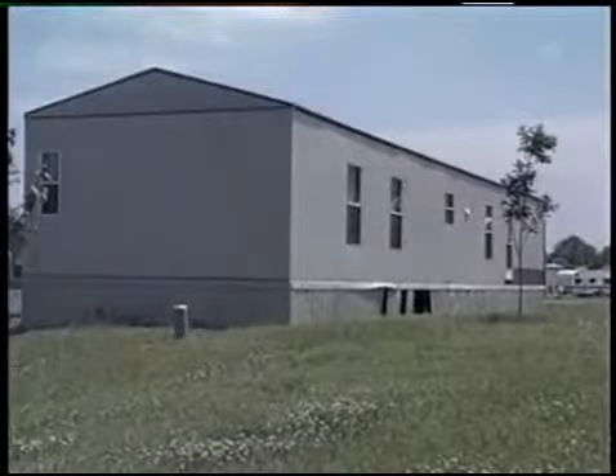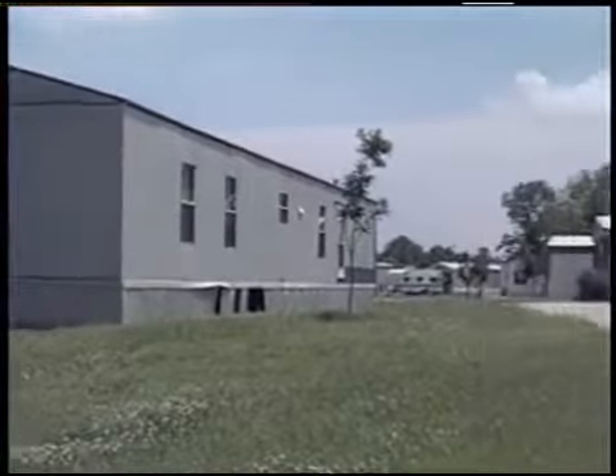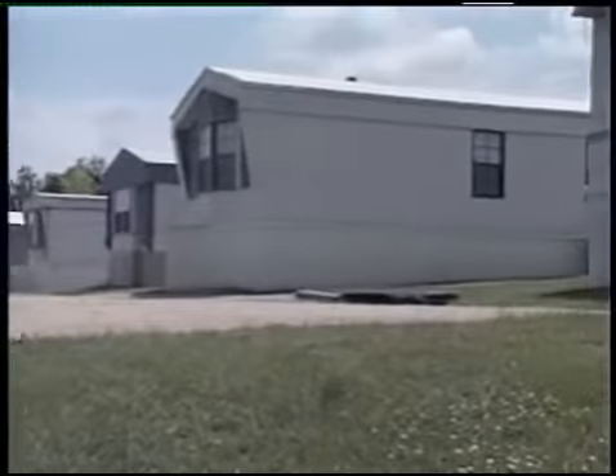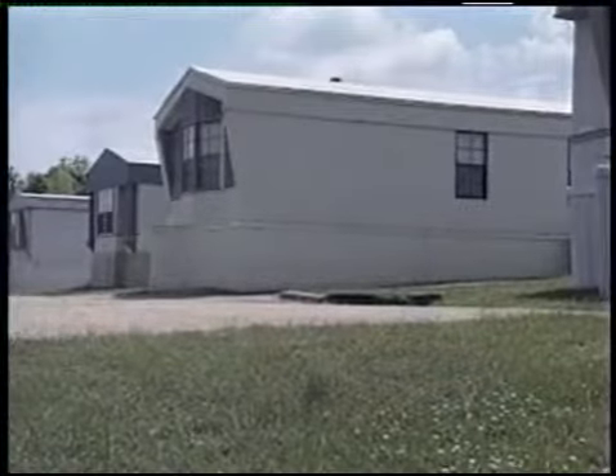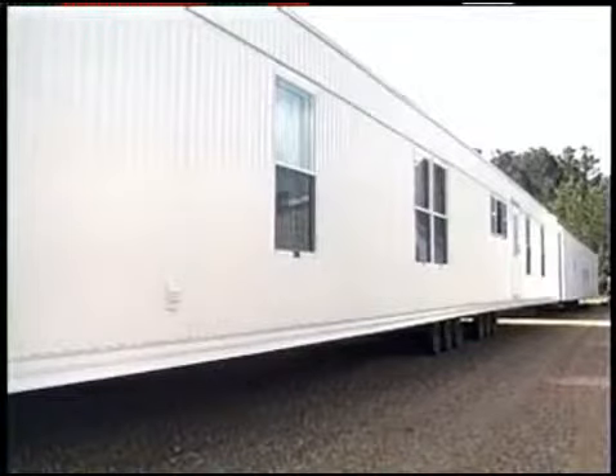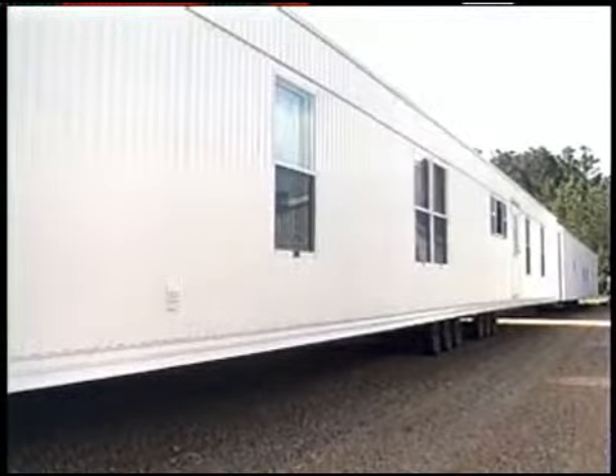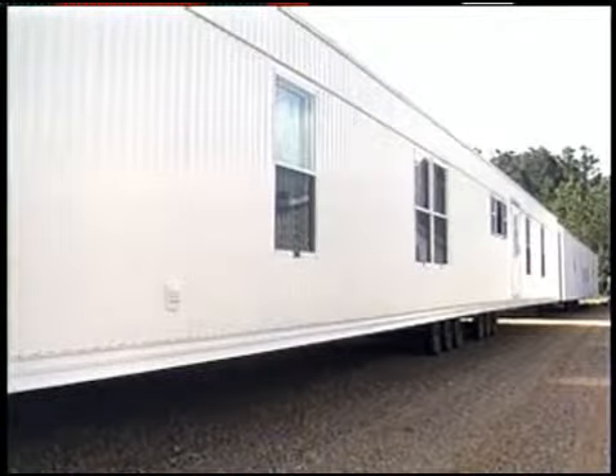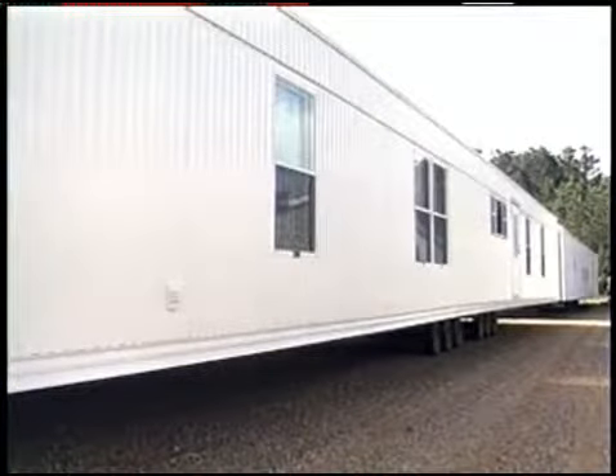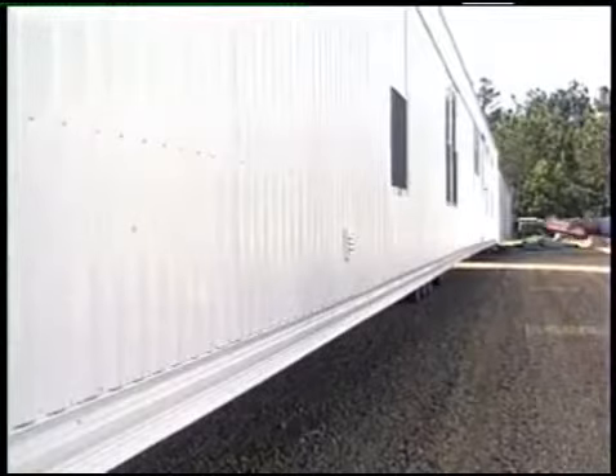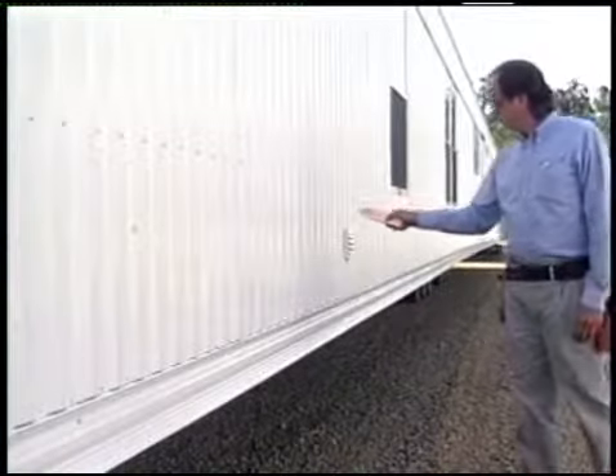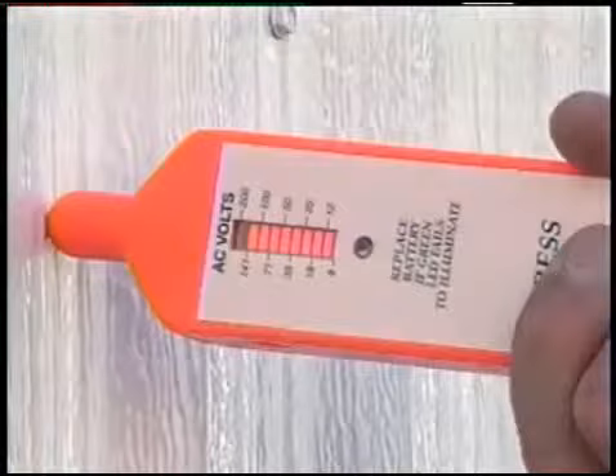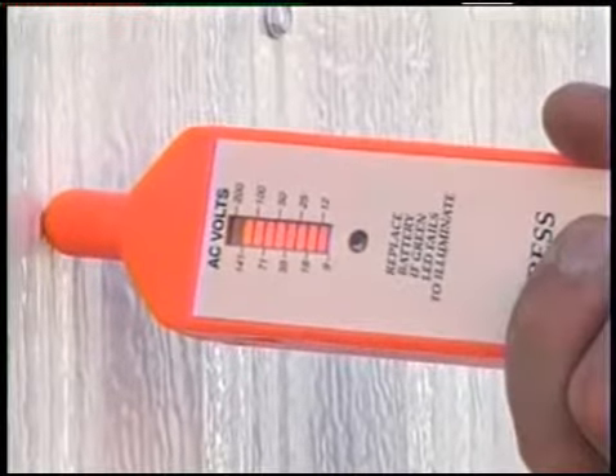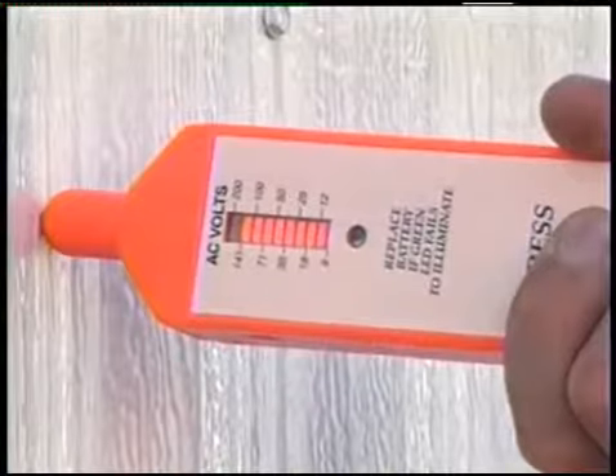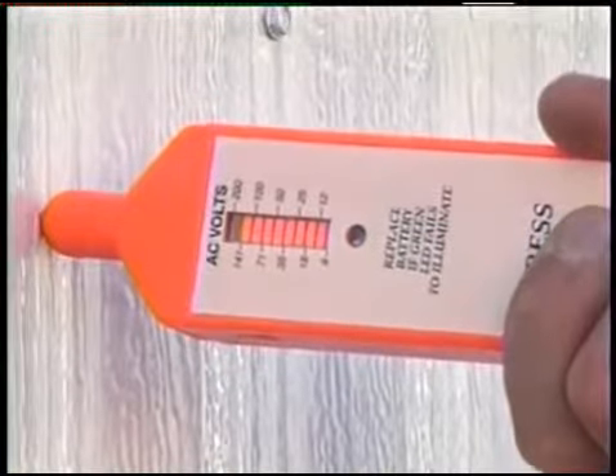A large surface such as this will give a higher reading than we get on a small gauge wire pair. This is true because the F.V.D. makes use of the coupling through the small capacitance between the F.V.D. probe and the source. The larger the source then, the more capacitance is present, and the greater will be the coupling. This mobile home has been purposely energized to 120 volts, as would be common in case of a power fault within the structure. Our F.V.D. is indicating considerably more than 120 volts.